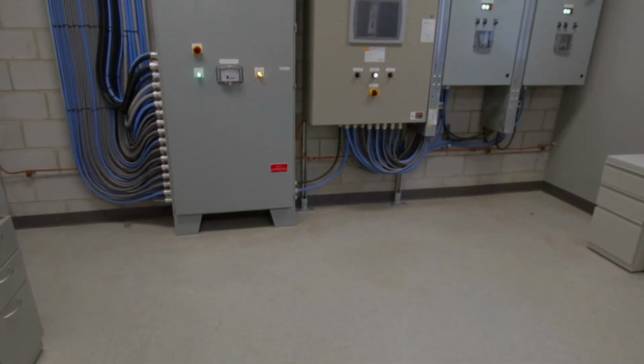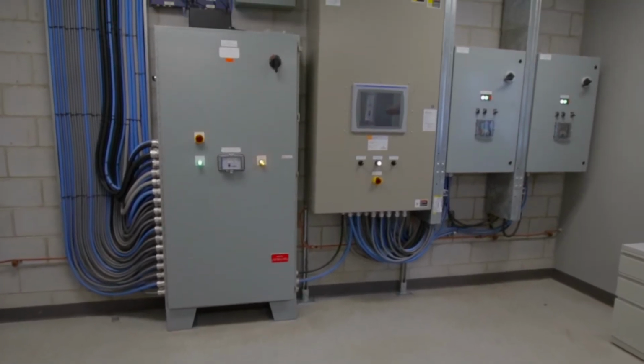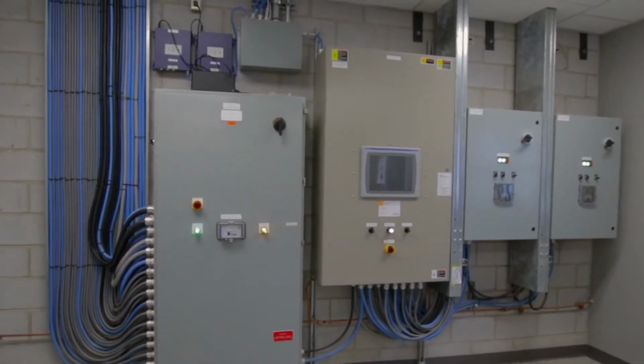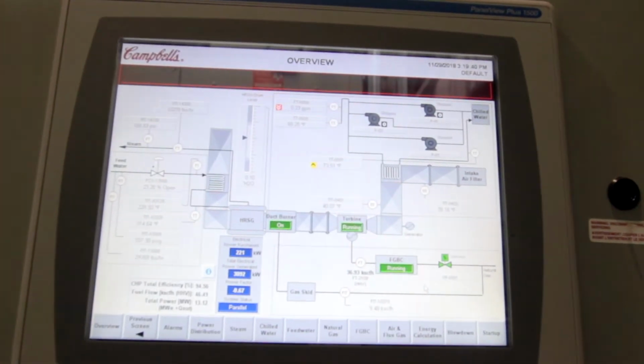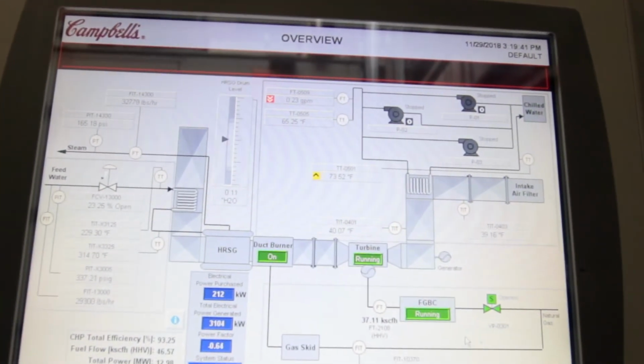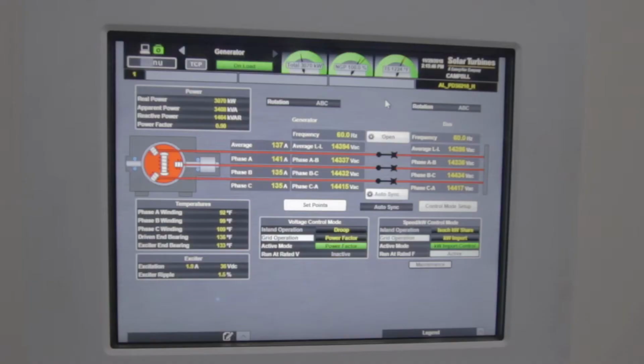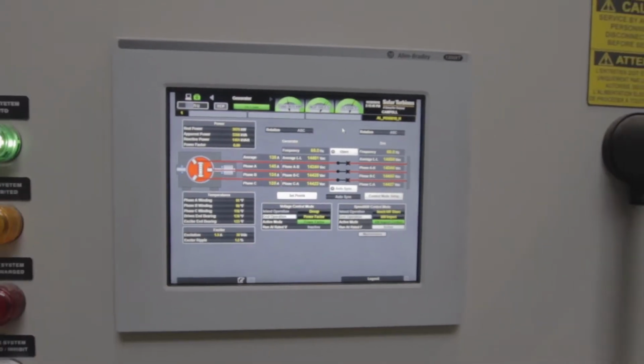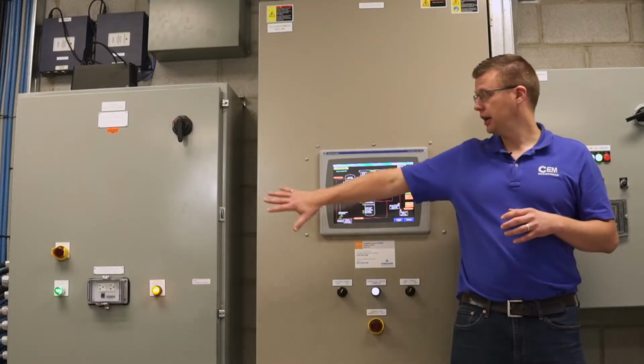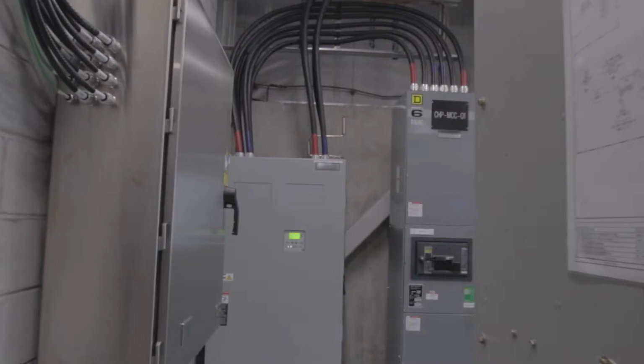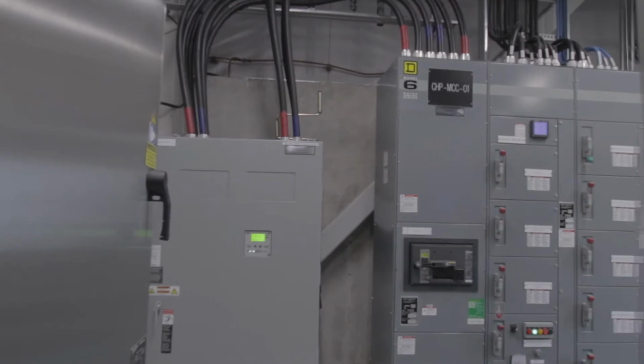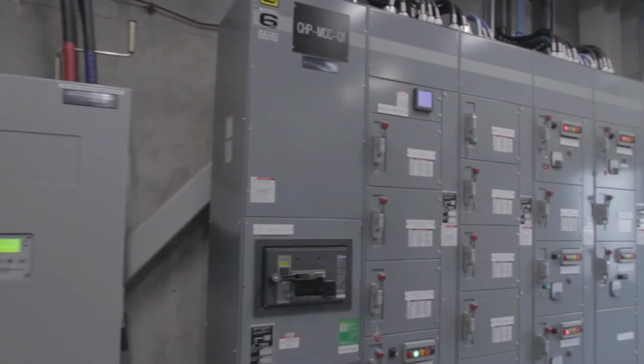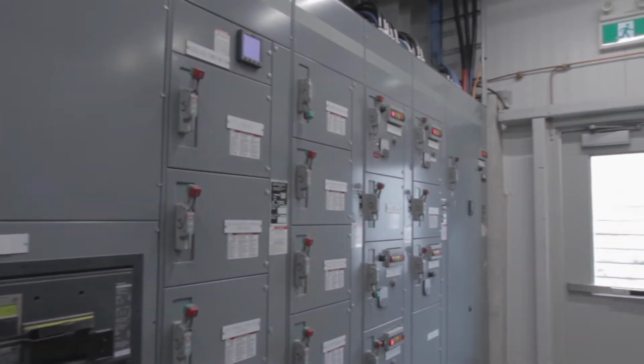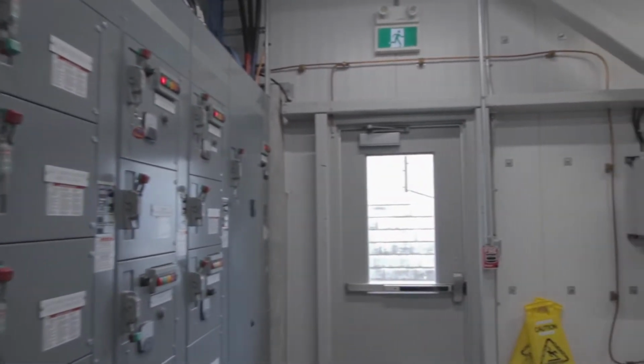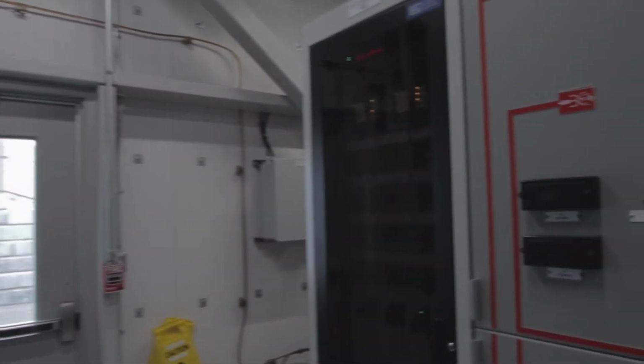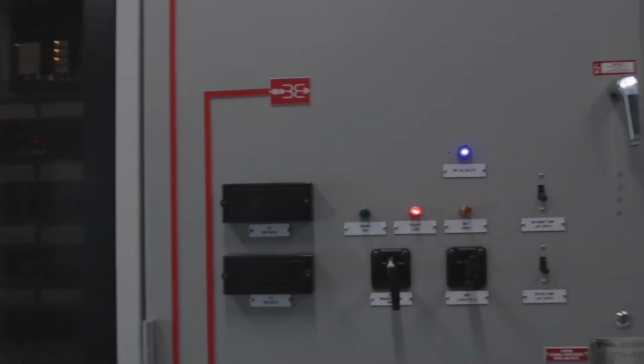Within the Co Gen plant, each big piece of equipment, the turbine, the heat recovery steam generator, the gas compressor, they all have their own dedicated controller, but like any good team, they have to work together. And so to make them work together, we have a balance of plant supervisory control system. The guts of it are right here, and there's a user interface in the control room. And it really brings together all the elements of the system, including any balance of plant meters or control valves or any other elements. And it provides the operator a real interface in terms of what's happening in the system.